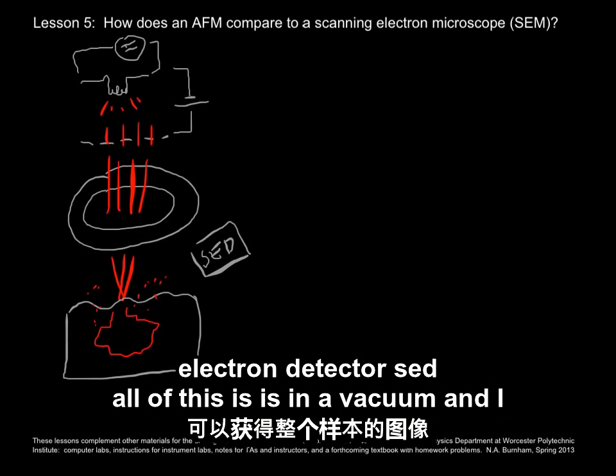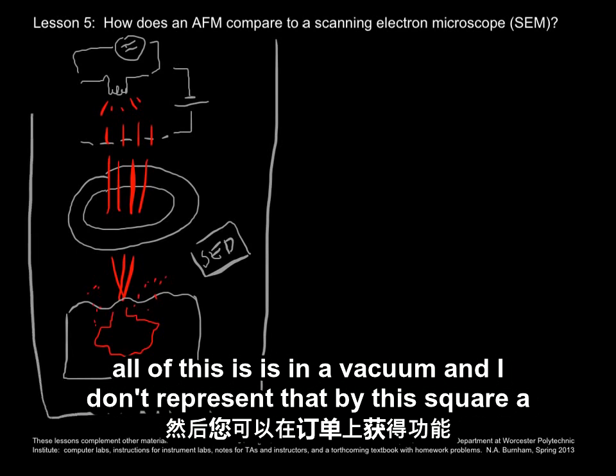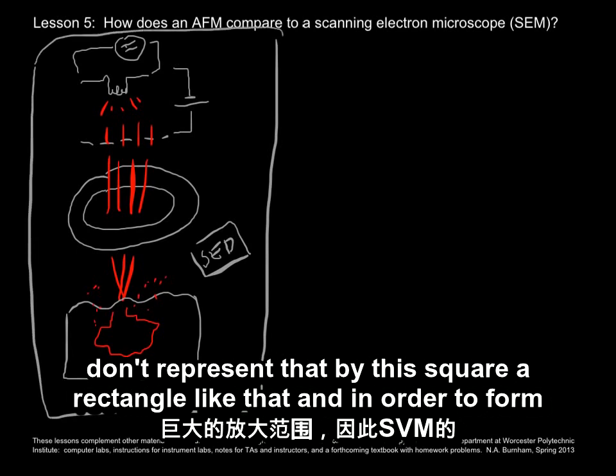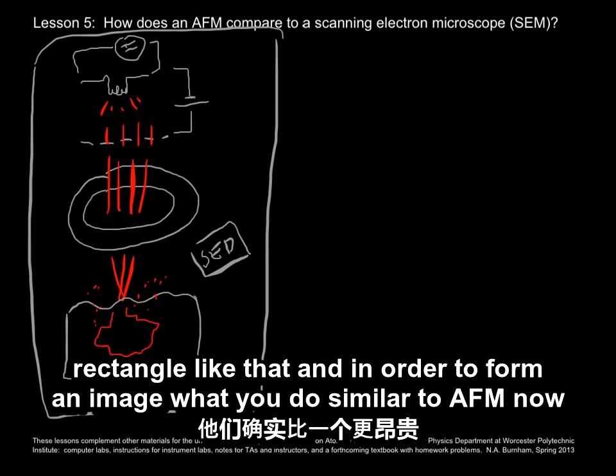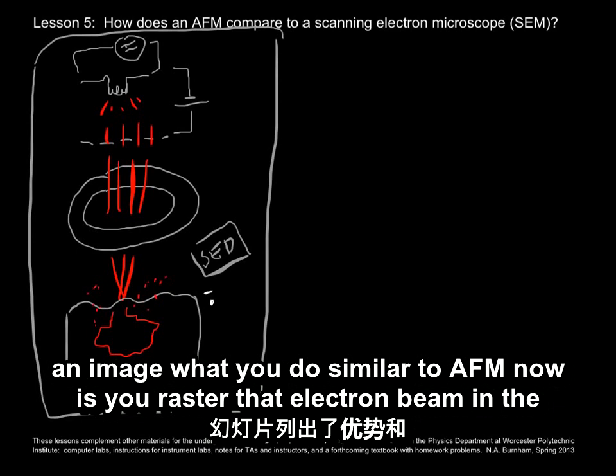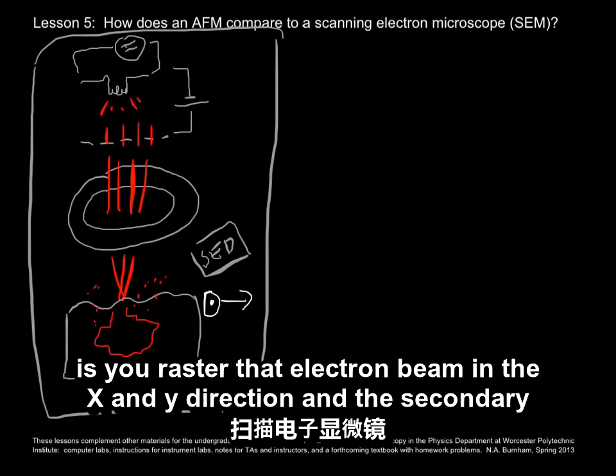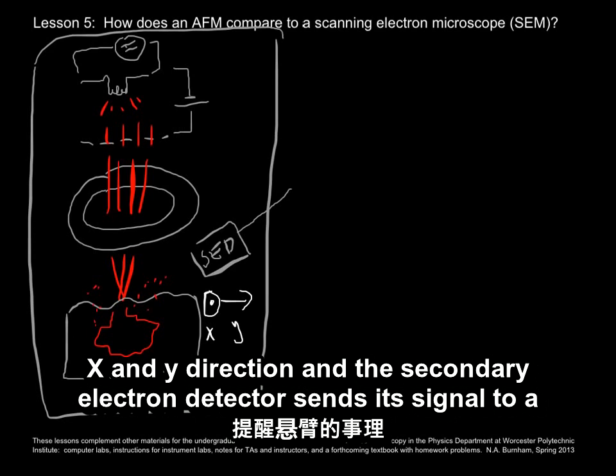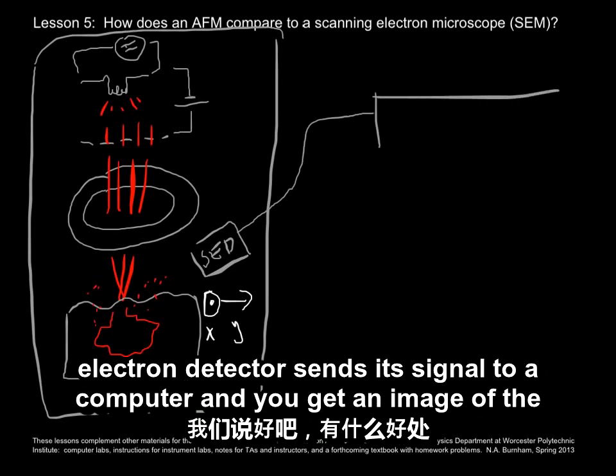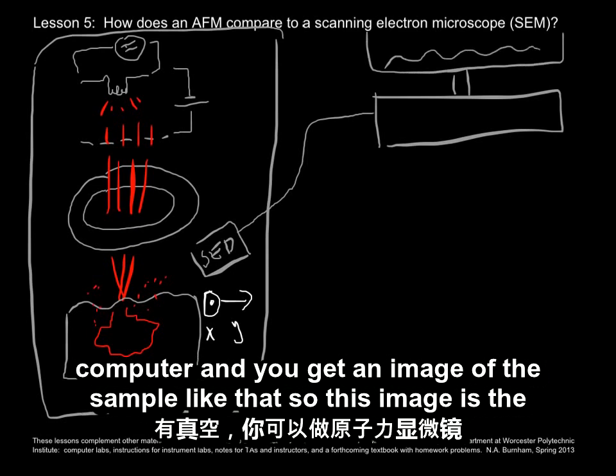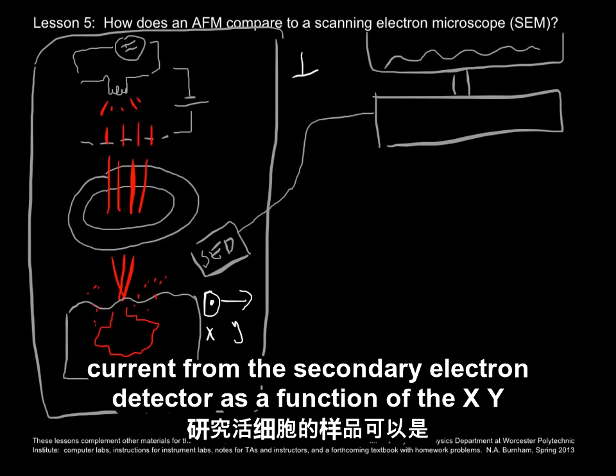All of this is in a vacuum. To form an image, similar to AFM, you raster the electron beam in the x and y directions, and the secondary electron detector sends its signal to a computer, giving you an image of the sample. This image is the current from the secondary electron detector as a function of the x-y position of the beam.